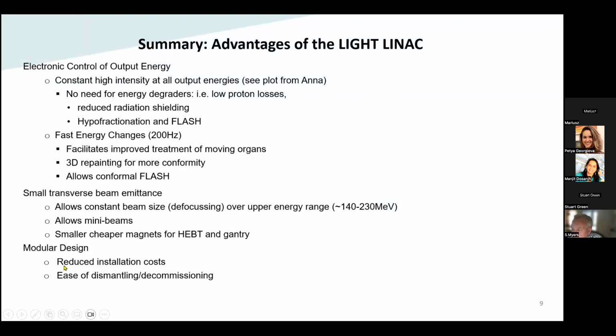The advantages of the light linac. This is summarizing what I've just said. Electronic control of output energy allows you to have a constant high intensity at all output energies, and you'll see a plot of this from Anna. You don't need these energy degraders, which means you have low proton losses. Because of the low proton losses, you've got reduced radiation shielding. And because of the high intensities throughout the range, you can do hypofractionation and flash.